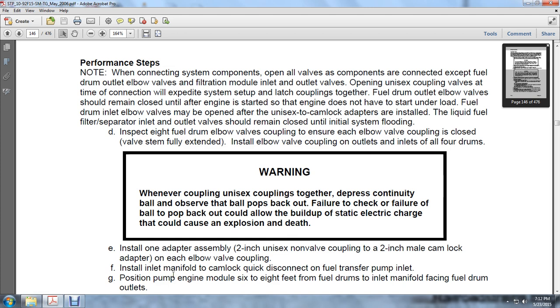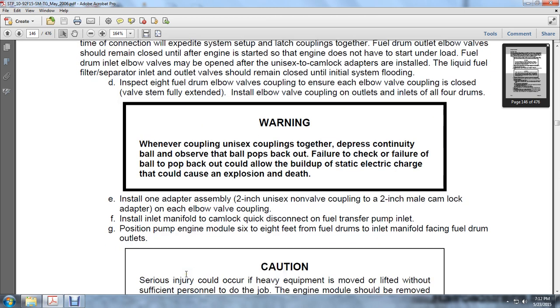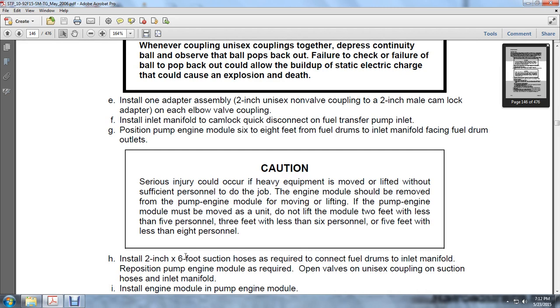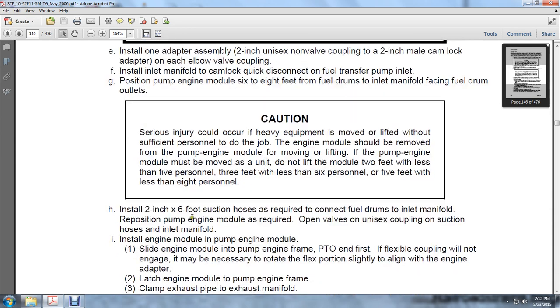Position the pump and engine module 6 to 8 feet from the fuel drums, with the inlet manifold facing the fuel drum outlets. Caution: serious injury could occur if heavy equipment is moved or lifted without sufficient personnel to do the job. The engine module should be removed from the pump engine module before moving and lifting. If the pump engine module must be moved as a unit, do not lift it more than 2 feet with less than 5 personnel, 3 feet with less than 6 personnel, or 5 feet with less than 8 personnel. Install 2-inch by 6-foot suction hoses as required to connect the fuel drum to the manifold.